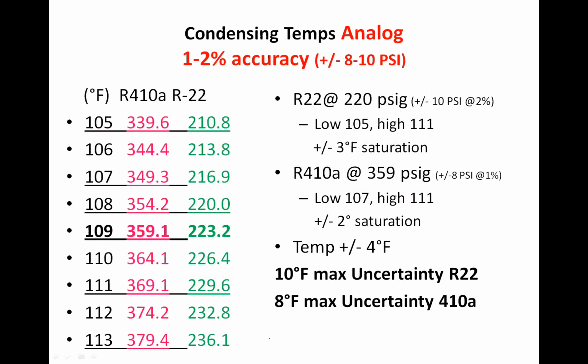Just to give you an idea here of the typical analog gauge, what this means to us, if we were to take R22 at 220 psi, right? So right at the top there, 220 psi, at plus or minus 10 psi, okay? So we're at 220 there. The low here would be 220 down to 210, right? And then 220 up to 230, okay? So these are the two we're going to look at right here. Well, again, what did I tell you that Energy Star determined we need to be within? Plus or minus 3 degrees. Well, just look right here from 108 down 10, that drops 5 psi. Right there's 3 degrees that way, and right here's another 3 degrees this way, right? So we're already talking plus or minus 3 degrees of saturation. We have a temperature uncertainty of plus or minus 4 degrees. That makes a total uncertainty of 10 degrees of uncertainty. There's no way with an analog gauge set that we could even be close.